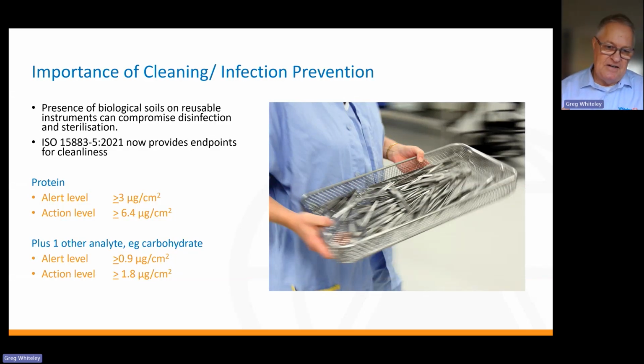So anything less than that, 3 micrograms per centimetre squared, is basically no trouble at all or acceptable. If you've got above that 3 and less than a 6.4, well, you need to revise what you're doing. If you've got more than 6.4, it's a fail and you'll probably need to do a recall on those devices. And then under the standards, particularly 15883, there's also a second analyte system you can use. You can do carbohydrate. You can also do ATP testing. So there's an array of things.